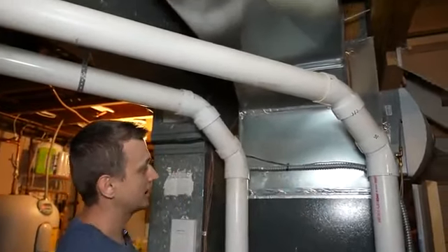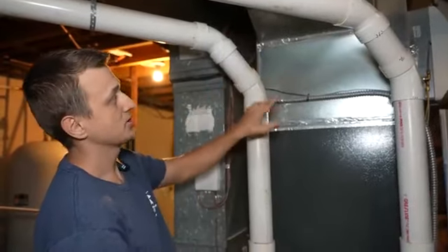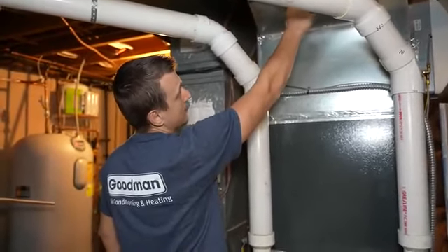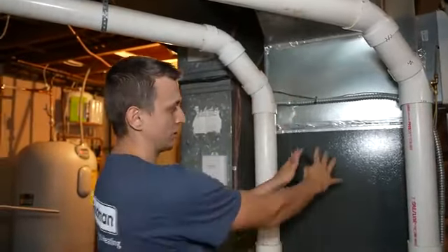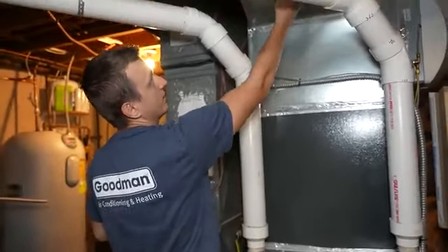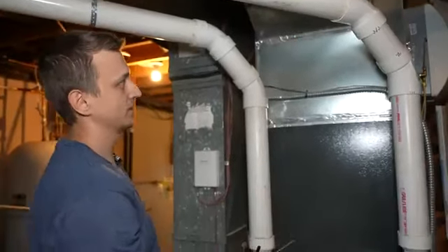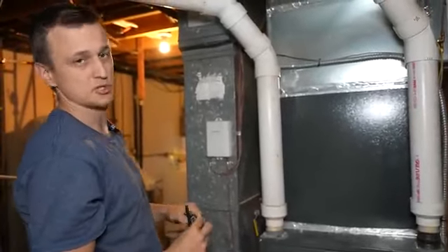And sometimes you get lucky, if this duct has ever been cleaned, they'll leave little plugs on your ductwork, little black plugs. You can just stick a thermometer in there. But I am not that lucky. So my options are either drill a small hole somewhere in the supply trunk, a little bit higher. You don't want to be drilling where the A coil is, not even close. Go higher, like either here or here. Stick your thermometer in and get a reading. So what I'm going to do is simply go find a vent, and I'll stick my thermometer into the vent and see what temperature we're getting.